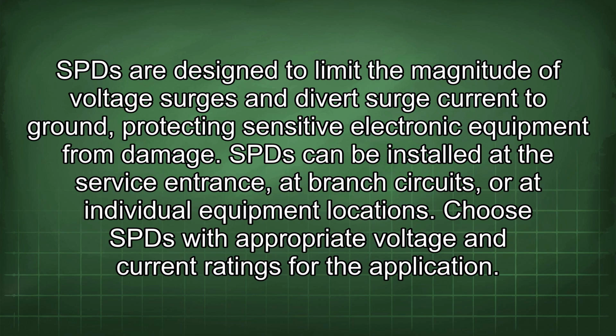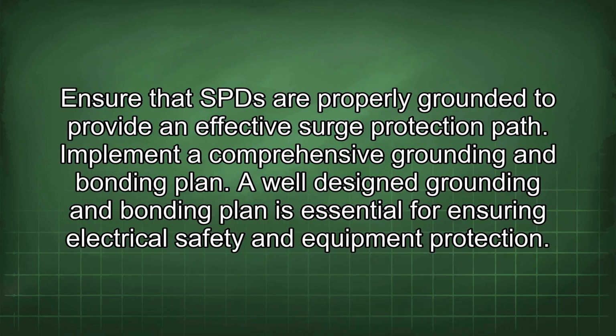SPD can be installed at the service entrance, at branch circuits, or at individual equipment locations. Choose SPD with appropriate voltage and current ratings for the application. Ensure that SPD are properly grounded to provide an effective surge protection path. Implement a comprehensive grounding and bonding plan. A well-designed grounding and bonding plan is essential for ensuring electrical safety and equipment protection.